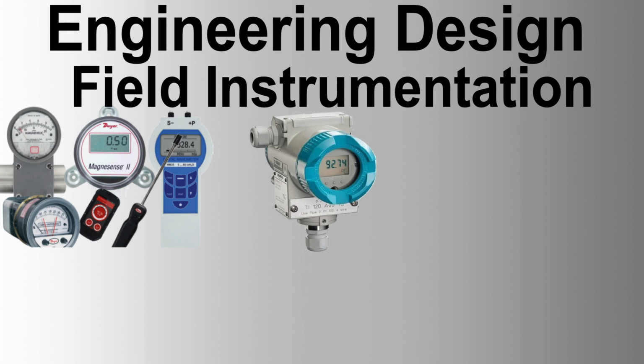Instrumentation impulse tubing, half-inch by 0.065, others, 1/4 inch by 0.049, vents and drains, 1/4 inch by 0.035. The tube wall thickness, finish, and roundness must be checked against the fitting manufacturer's requirements. Carbon steel, half-hard copper, and aluminum tube must not be used.